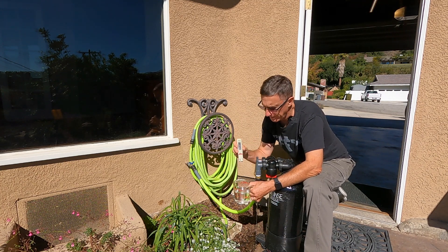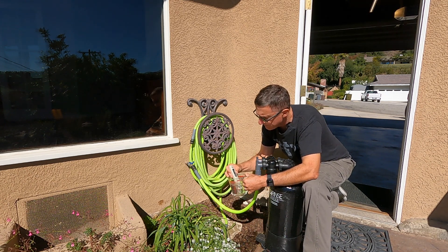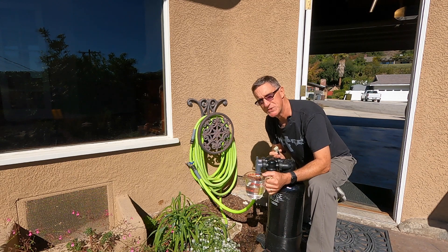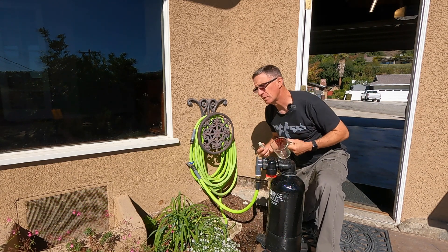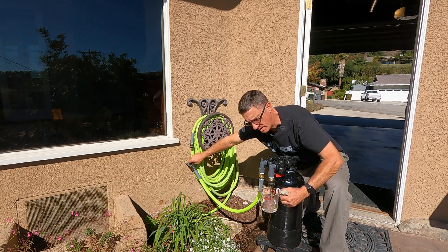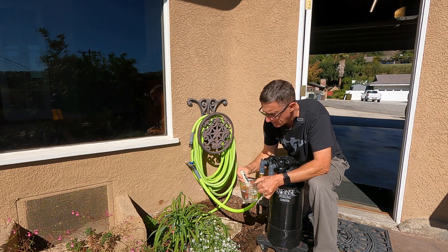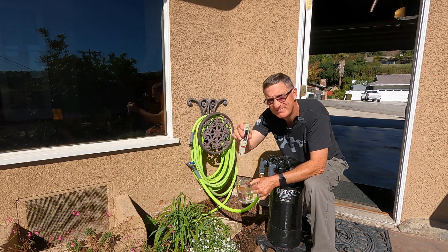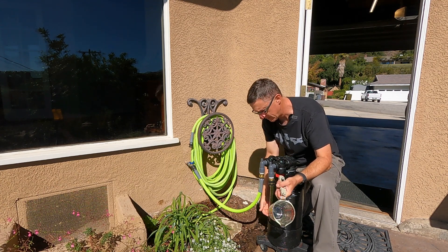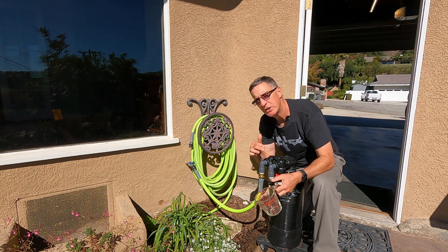You don't submerse the meter past that red line — you're basically hitting the sensor down there. The initial reading is 105, which is not bad. I'm going to flush it a little more because I suspect there's water in there that's been sitting and it's probably super pure. After flushing, the reading is 290. What happened was the stagnant sitting water in the bed was getting nicely deionized, so it came out super pure first — which is another testament to the fact that you've got to run this slow.